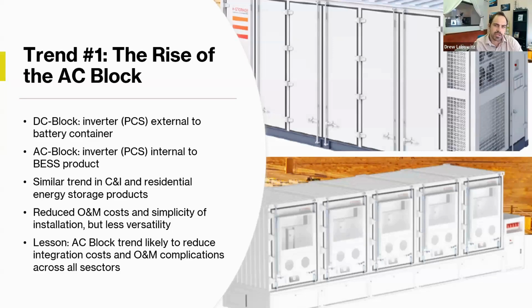That trend has permeated residential, commercial, industrial, and here we're showing utility scale. There are a few reasons they're doing it this way. One, it makes fewer components on site, so fewer things to hook up. Two, there's simplicity so you don't have a different brand inverter talking to a control system, talking to the battery product—you just have that integrated unit. Lastly, on an overall site basis, if you look at the acreage, using these AC block products you can have a higher density of megawatts or megawatt hours per acre. All these things combined make it a valuable option.